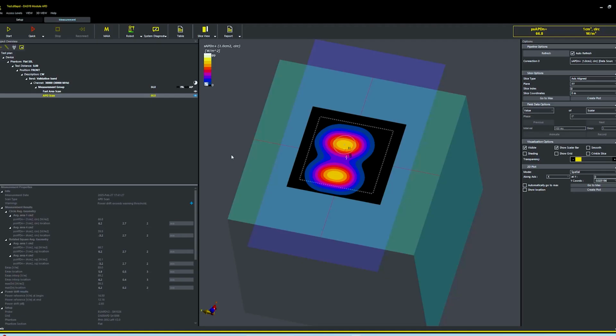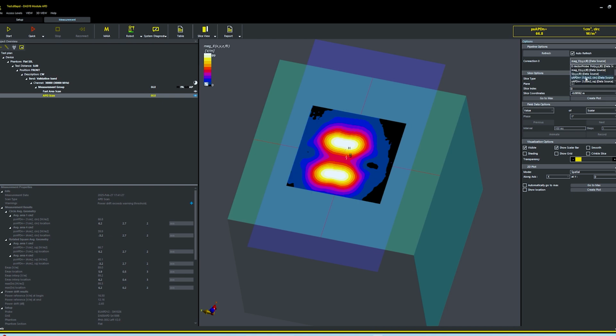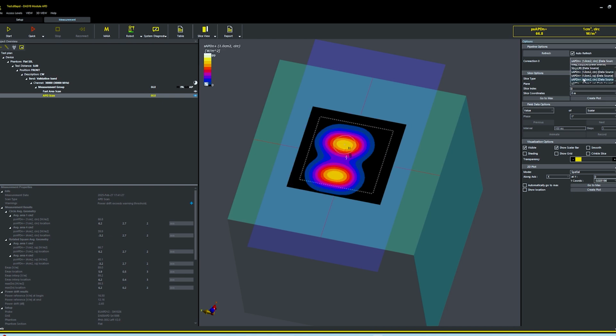The measurements are now finished and we can quickly visualize the results. The 1 cm square and 4 cm square circular averaged APD value for this source works out to 66.8 and 39.9 watt per meter square. The deviation from the target values are 0.35 and 0.2 dB respectively. These are pretty good considering the high frequency and resulting field gradients involved in this measurement. The available field display quantities include the field magnitudes as well as the circular and square averaged power density.